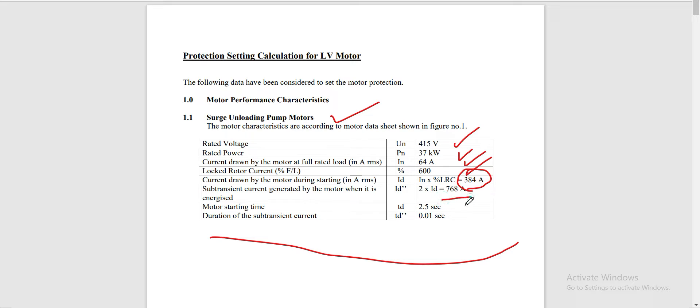768 amperes is the sub-transient current generated by the motor when it is energized. This is twice the value of the lock rotor current — multiply 2 times 384 to get 768 amperes. Our motor starting time is 2.5 seconds and the duration of the sub-transient current is 0.01 seconds.